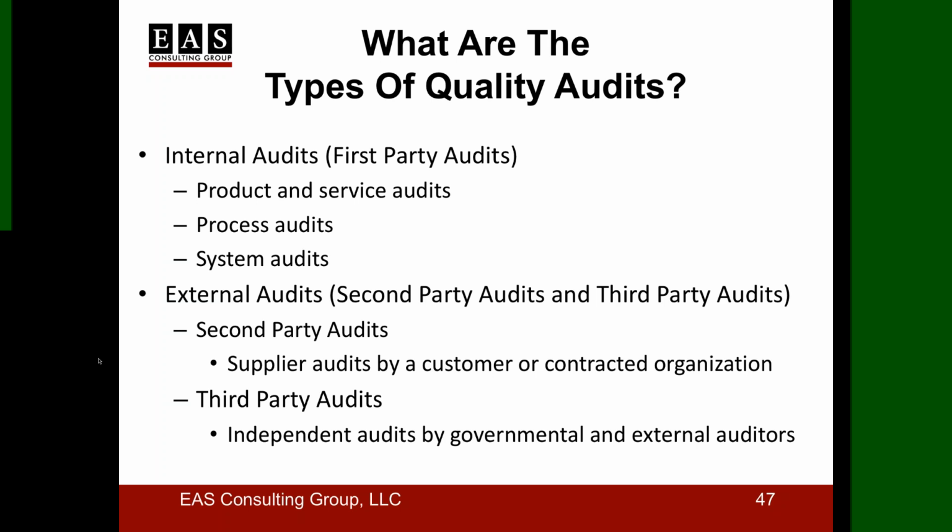really are, on the FDA side, let's just say, second-party audits, which are audits that you do for your supplier. So under purchasing controls, which is 21 CFR 820.50, you have to evaluate your suppliers, contractors, and consultants.